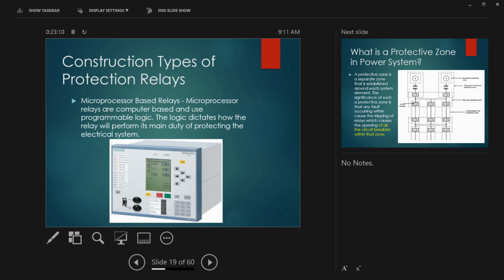So, microprocessor based, it is a relay that is computer based with programmable logic. No need for you to move those bolts and nuts to put it on the desired tap that you want. And of course, the speed of the contact tripping can be programmed as well. So the logic dictates how the relay will perform its main duty of protecting the electrical system. You can put all your logic, AND gates, OR gates, and put them together, and you already have the mimic bus showing the current and the voltage of different buses. That's what we're gonna do.